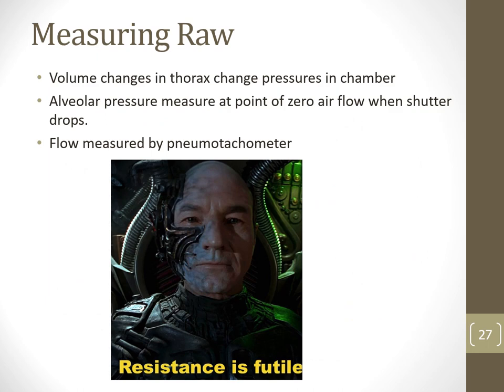So volume changes in the thoracic pressure in the chamber. So as you take a deep breath in, your thorax should change in the chamber, and so that's going to change the chamber pressure. Alveolar pressure will have zero airflow when the shutter drops. So then we'll have zero airflow, and then we're just looking at the flow pretty much in the pneumotach. And the pneumotach will tell us what's going on with their flow rates there.